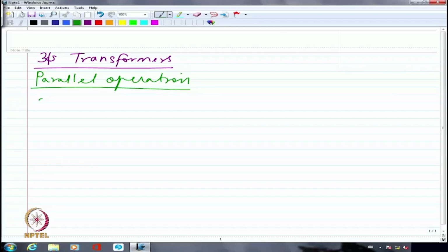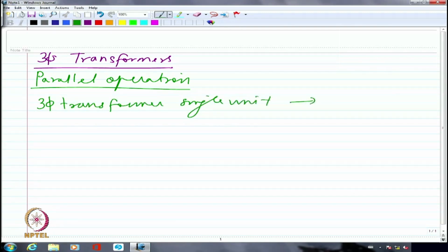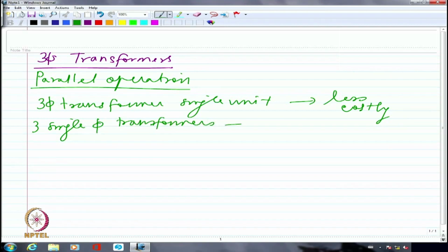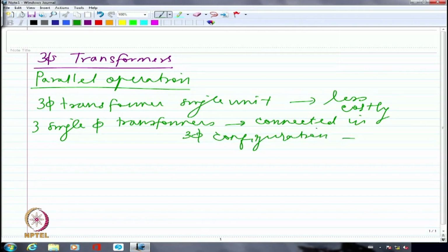It can be connected in star or delta, that's a single unit of three-phase transformer. This will actually save on the cost, so it is less costly. Whereas if I look at three single-phase transformers connected ultimately as a three-phase transformer, so this will be connected in three-phase configuration, this will be generally more costly or costlier. That is because you are essentially looking at individual units separately being bought and connected as per your requirement.